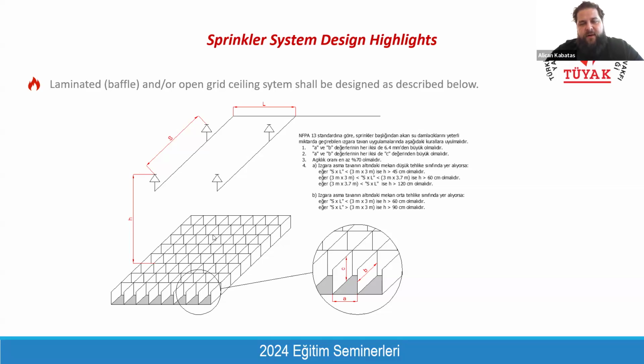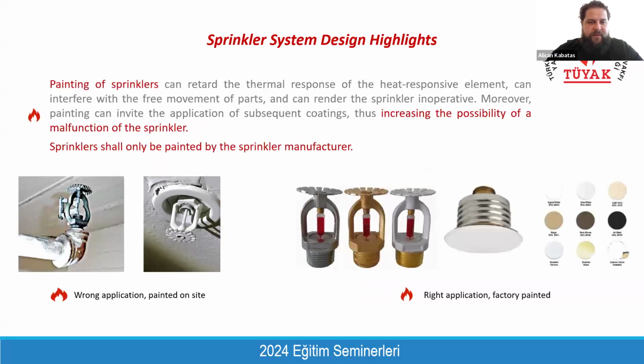If you are not aware of these rules, and if you design your ceiling so that it does not fulfill these requirements, at the end of the day, the fire consultant of your project will require you to provide an additional level of sprinkler system beneath the ceiling, and it will change your design, it will change the look of your ceiling. That's why it is also important.